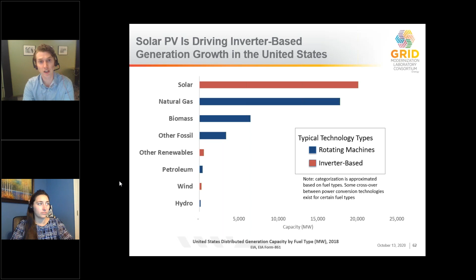When I say inverters can't sustain an island, I'm caveating that these are grid-interactive inverters certified to a specific certification, UL 1741, which tests specifically that they are not able to sustain an island and that they can detect and disconnect from the system. There are other inverter designs intended for island operation, and that could even be within the same inverter device, switching over to an intentional island mode. But in that intentional island mode, it's not operating in the mode certified for grid-interactive operation. So yes, certain designs can sustain islands, but largely when utilities interconnect inverters, they're assuring they're not able to sustain an island.